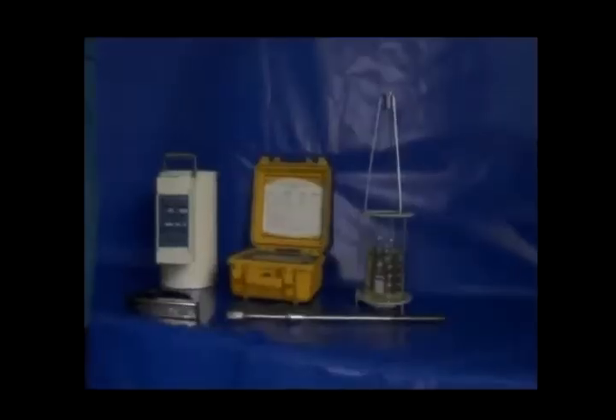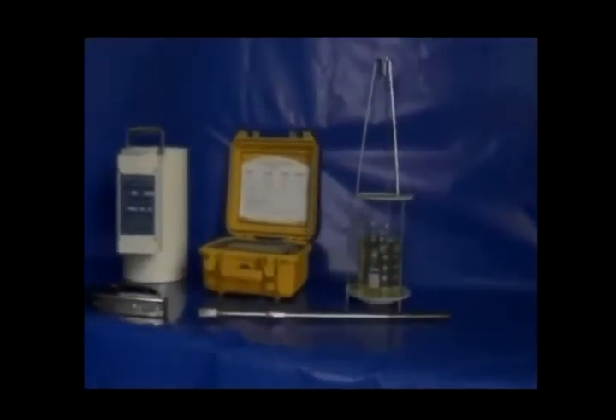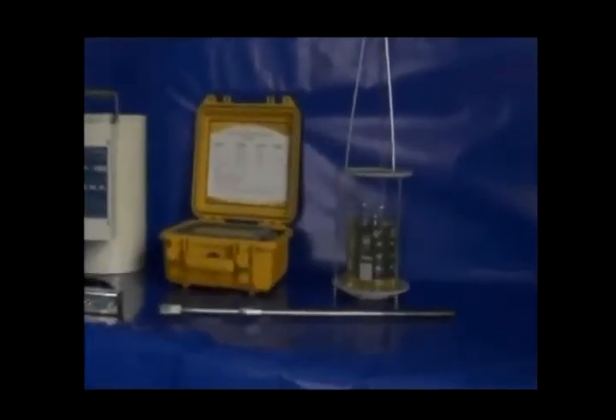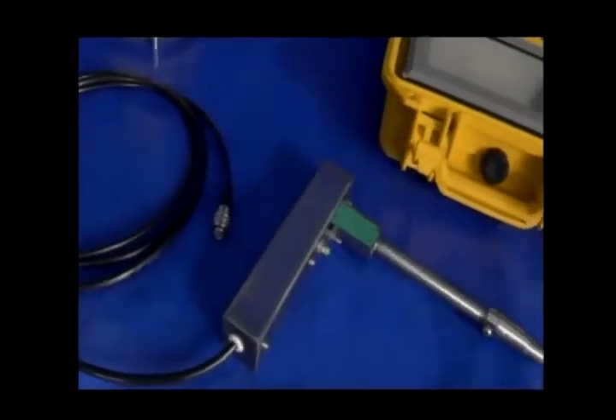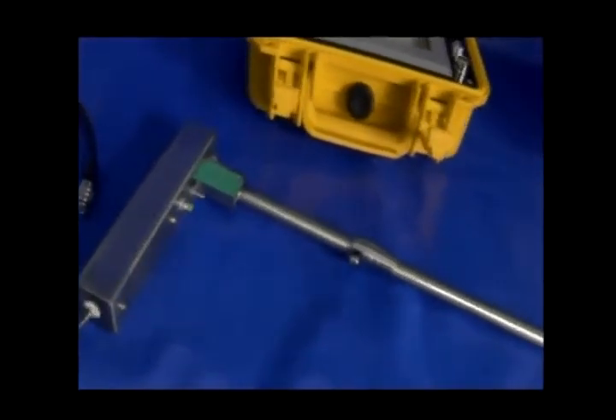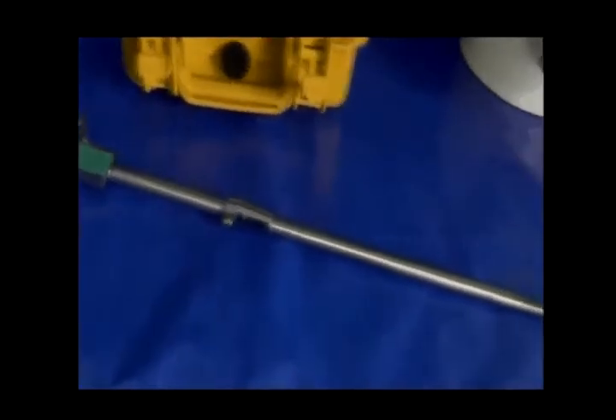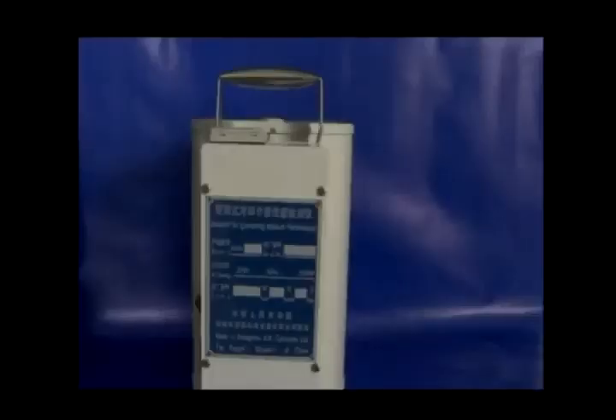Second, the position of the located clip on the probe must be accurate. The distance between the bottom of the clip and the head of the probe is 402 mm. Please install the clip in the relative position on the new probe when the probe needs to be replaced.